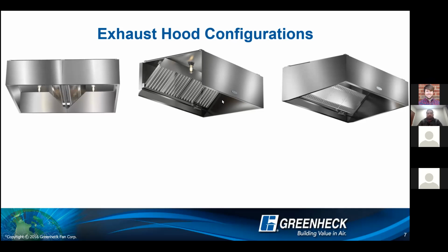The next hood configuration would be a double island, or a double wall canopy back-to-back in an island application. This is 2 wall canopy hoods hung back-to-back to each other for when you have back-to-back appliance lineups, so you can have that large capture footprint.